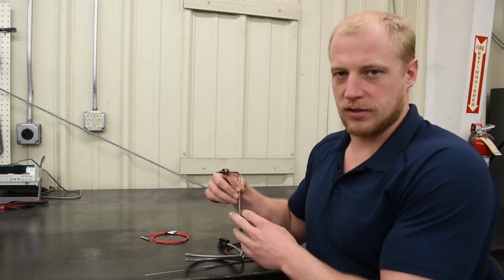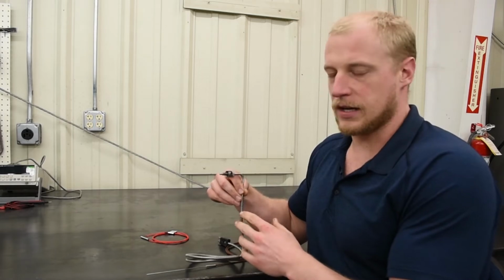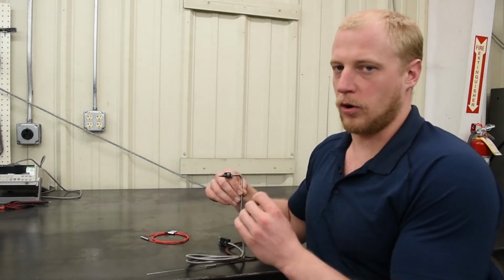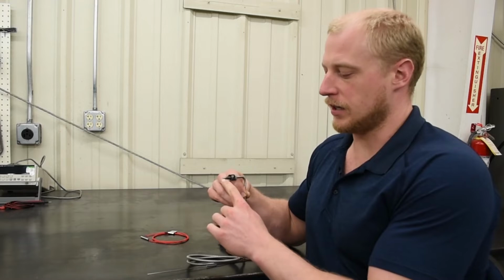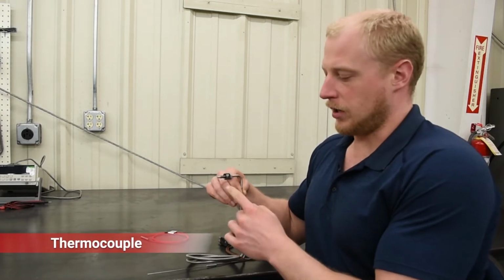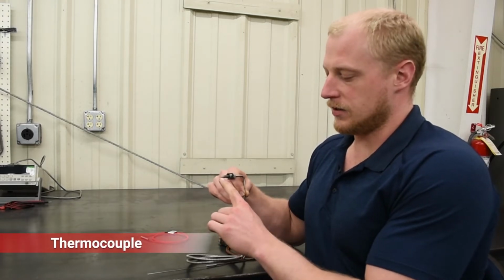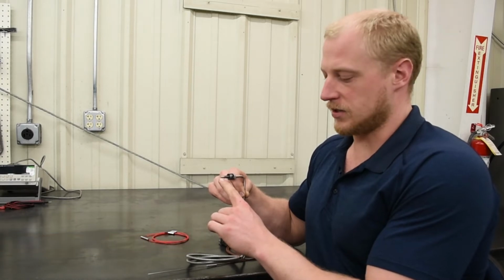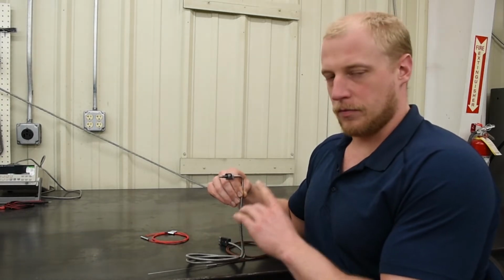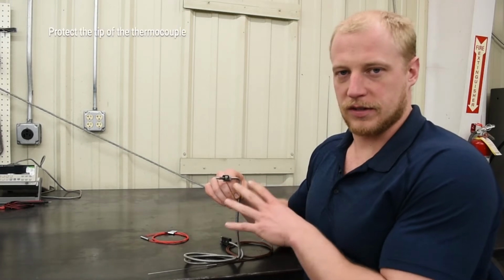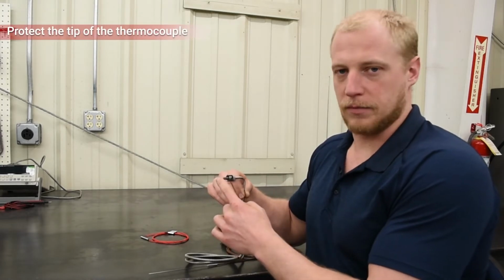For all temperature sensors, whether thermocouple or RTD, the actual sensing part is at the end of the tip. This is a thermocouple, and that junction is right there at the tip, which is where we're measuring temperature. So the most important part to protect on this sensor is the tip.